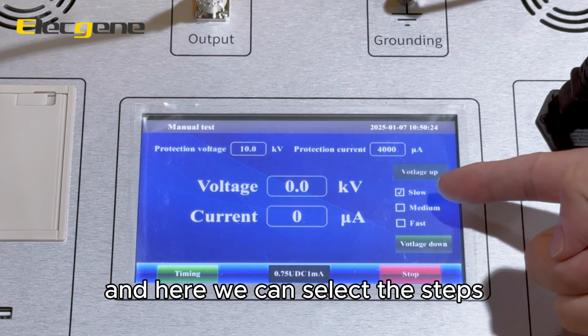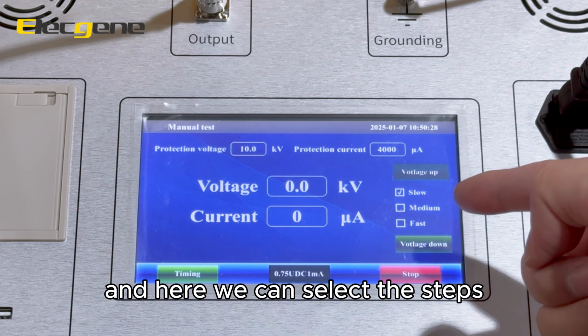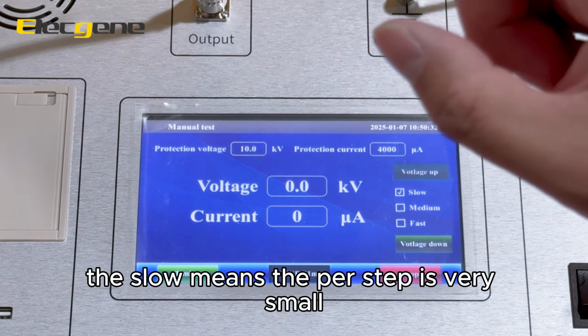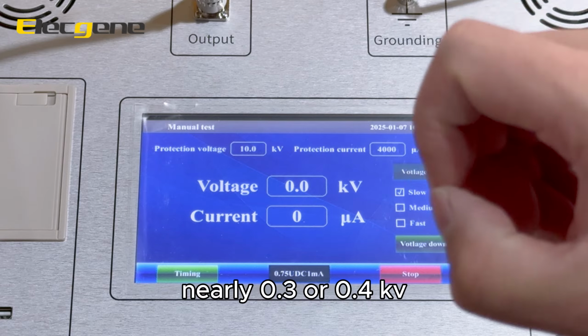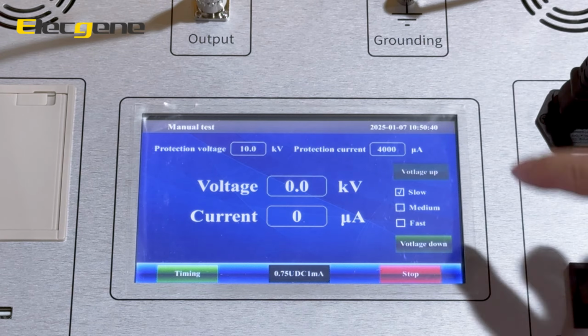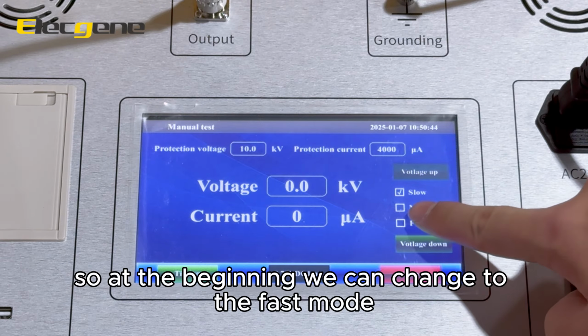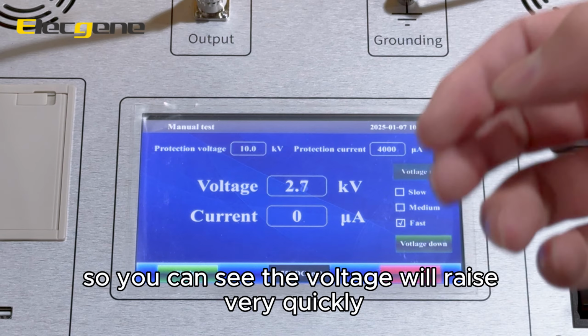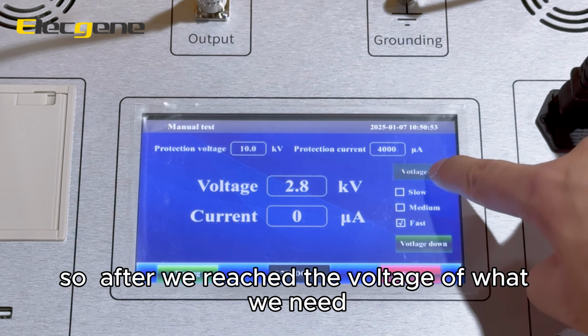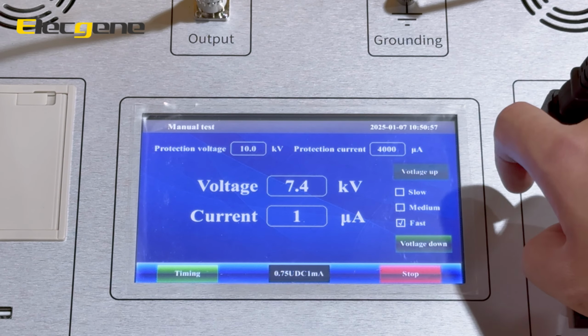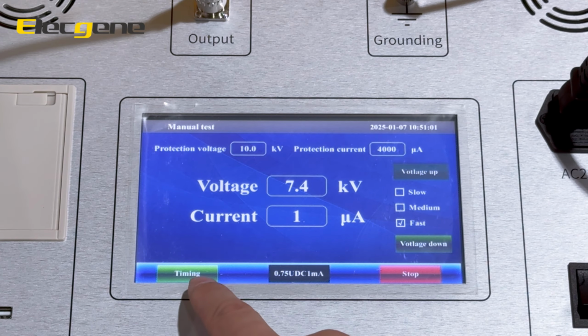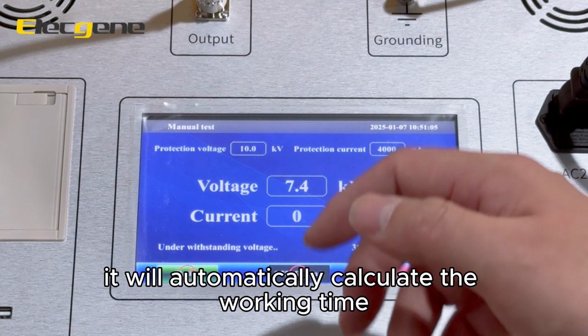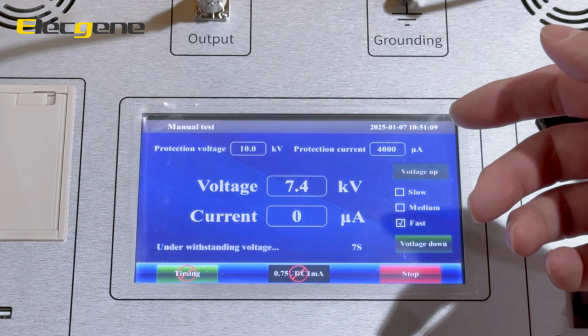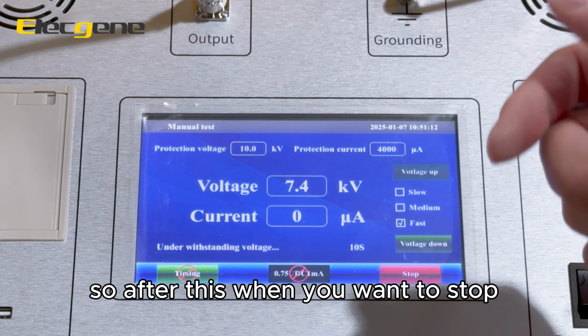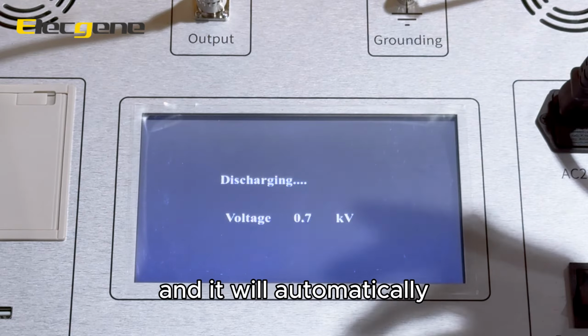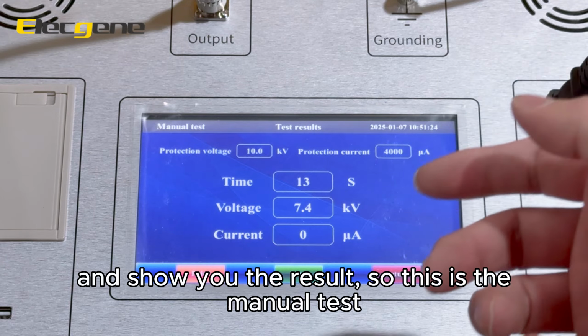You can see, in here we can select the steps. The slow means each step is very small, maybe nearly 0.3 or 0.4 kilovolts. So at the beginning, we can change to the fast mode here, and we press voltage up. So you can see the voltage will rise very quickly. After we reach the voltage we need, we can press the timing. When you press the timing, it will automatically calculate the working time. When you want to stop, you just press stop, and it will automatically reduce the output voltage and show you the result. So this is the manual test.